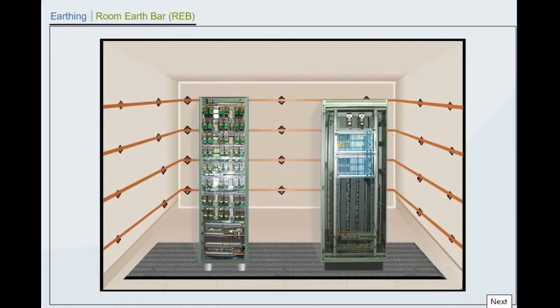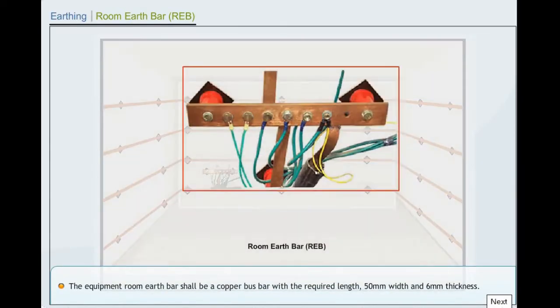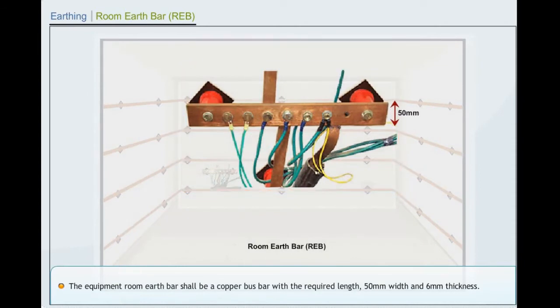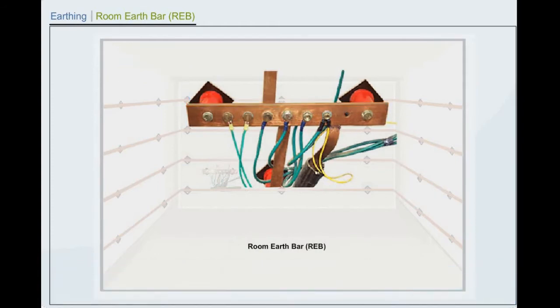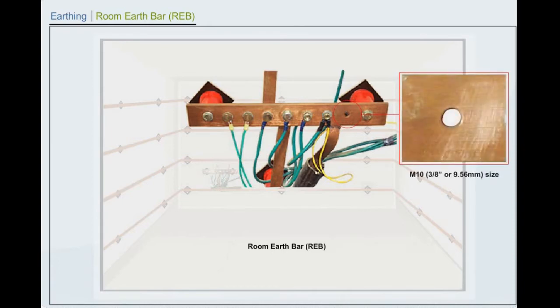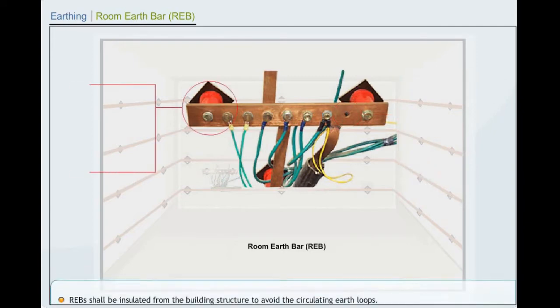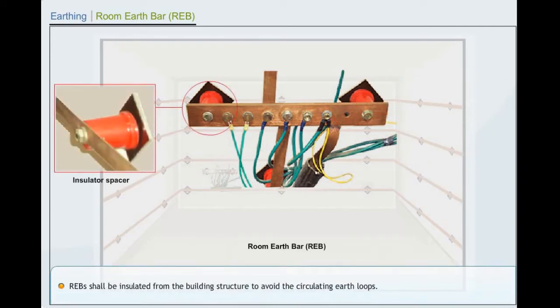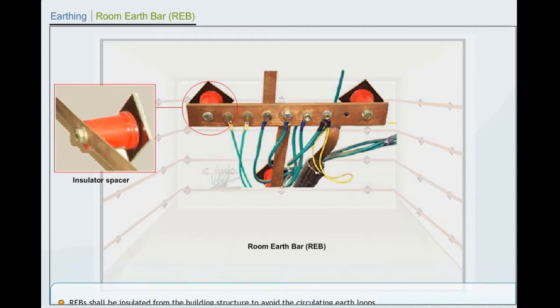Earthing. Room earth bar. The equipment room earth bar shall be a copper bus bar with the required length of 50 mm width and 6 mm thickness. The room earth bar shall be pre-drilled with a number of holes of M10 size suitable for termination of bolted cable lugs. Room earth bar shall be insulated from the building structure to avoid circulating earth loops.